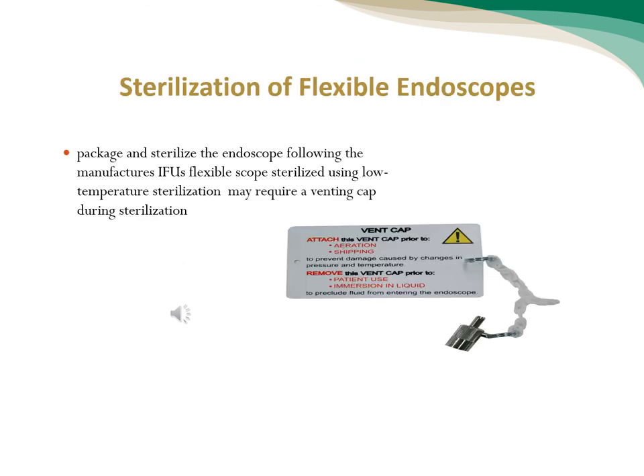Sterilization of flexible endoscopes: package and sterilize the endoscope following the manufacturer IFUs. Flexible endoscopes are sterilized using low-temperature sterilization and may require a venting cap during sterilization.